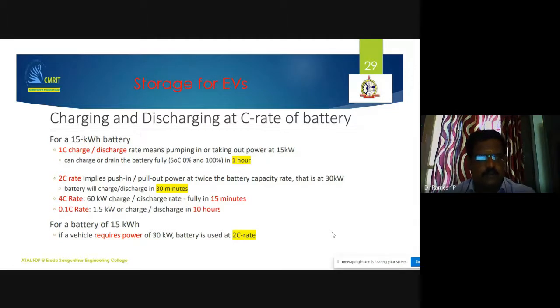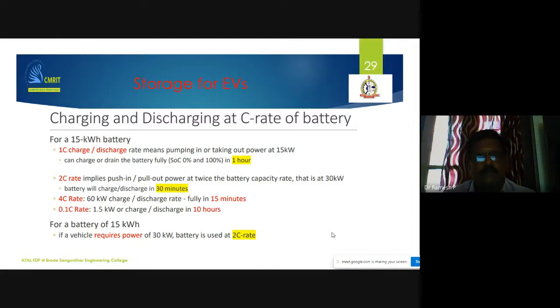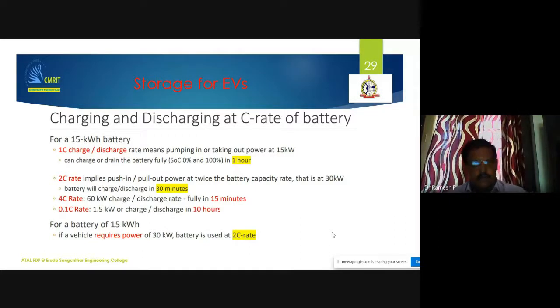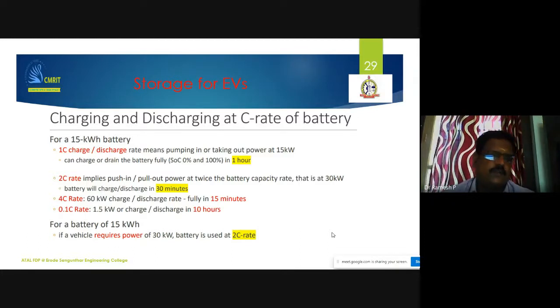Let's go through the process of 1C rating, charging or discharging. Discharge means SOC goes to 0%, charged means SOC comes to 100%. So you are varying the SOC from 0 to 100% within 1 hour. That is called 1C charging or discharging. If you have a 15 kilowatt hour battery and you charge it within one hour, that is 1C rating charging.